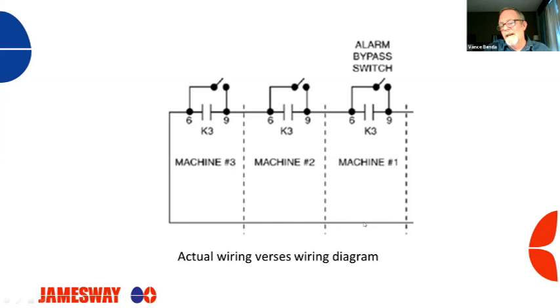Now, knowing that you have this connection right here in the real world, this is your black wire, and this is, say, your white wire, or maybe your red wire. On the last machine in the loop, this is going to be black and black, and black right here. On the last machine, this wire, the red wire or white wire, depending on what kind of two conductor you use, is going to be connected here. Now, knowing you have these connections here, you can easily, by disconnecting this connection, disconnecting this connection, and moving this wire up to here, eliminate a whole bunch of machines in that loop for troubleshooting purposes.